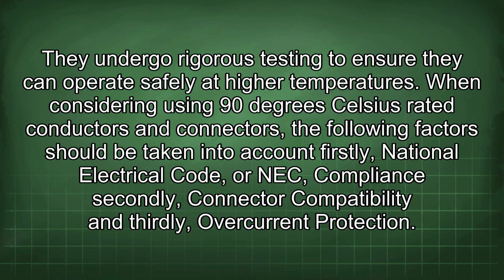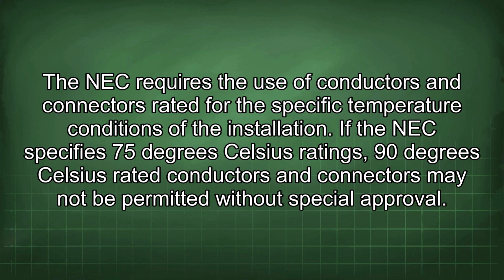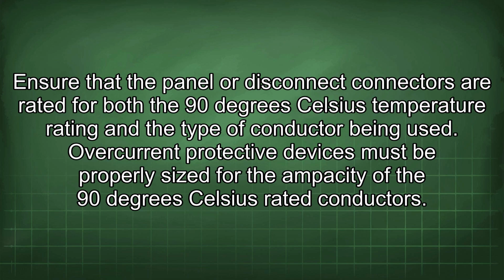When considering using 90 degrees Celsius rated conductors and connectors, the following factors should be taken into account. Firstly, National Electrical Code, or NEC, compliance. Secondly, connector compatibility, and thirdly, overcurrent protection. The NEC requires the use of conductors and connectors rated for the specific temperature conditions of the installation. If the NEC specifies 75 degrees Celsius ratings, 90 degrees Celsius rated conductors and connectors may not be permitted without special approval. Ensure that the panel or disconnect connectors are rated for both the 90 degrees Celsius temperature rating and the type of conductor being used.